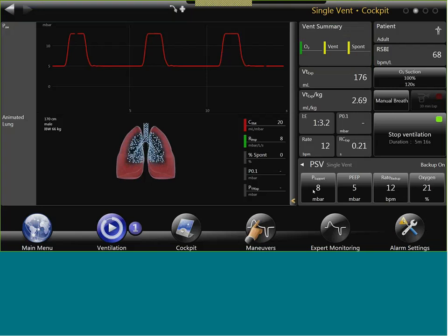We have some home care patients which are really dependent on the ventilator, where the bellavista is running 24 hours, 7 days a week. And so we haven't found out how long the bellavista is able to work continuously, because there is no time limit. You have to have an annual maintenance once a year. So I think that defines the break. So at least 1 year, the ventilator will run without any problems.